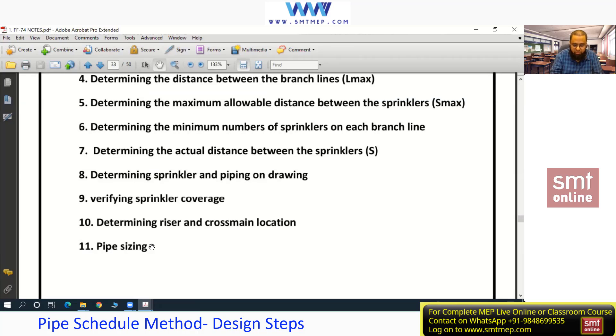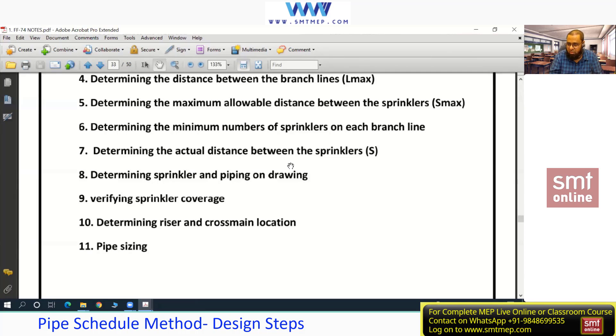Step 8: Determine the riser and cross main location — the riser location is based on the architectural shaft, which is decided by the architect. Step 9: Pipe sizing. In fire fighting design, pipe sizing is straightforward because we have ready-made code tables — based on the pipe material (steel or copper), the hazard, and the number of sprinklers, we can determine pipe size. We don't use a pipe sizer in fire fighting; we follow the code. Similar to plumbing, fire fighting design is not based on peak demand — in a sprinkler system, except for deluge systems, not all sprinklers activate at once. Pipe sizing is based on the code and probability, not peak demand — we follow the NFPA tables.